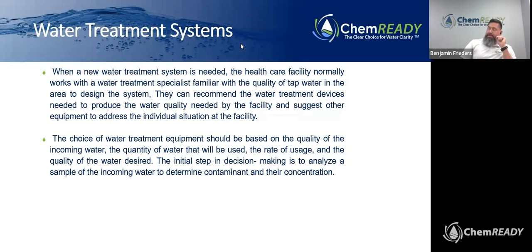And each area is different. So for example, GetChemREADY is based here in Twinsburg, Ohio. I live in Indianapolis, Indiana. The differences between water quality from the city between the Cleveland area itself and the Indianapolis area are vastly different. So if you're in Cleveland, you don't have to do a lot of treatment to get within the standards of utility water. Whereas if you're in Indiana, then you need to have some type of treatment to meet those utility water specs. So someone that is familiar with the area that your facility is located in is vitally important in terms of the decision to become compliant in terms of water quality treatment equipment.